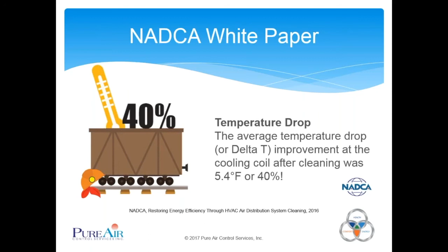So what they found on average with cleaning the coils was that the average temperature drop improvement at the cooling coil after cleaning was 5.4 degrees Fahrenheit, or about 40%. And the cooling capacity, or BTU output or heat transfer rate, the average cooling capacity improvement was 225%.